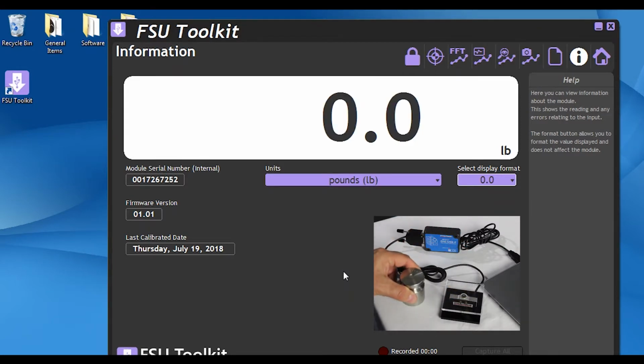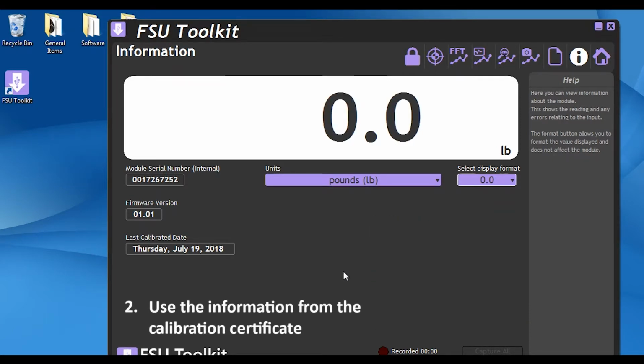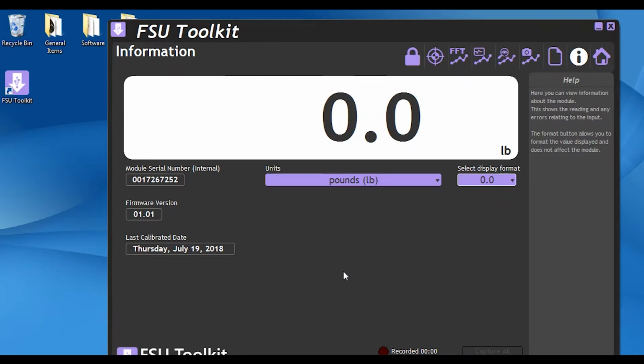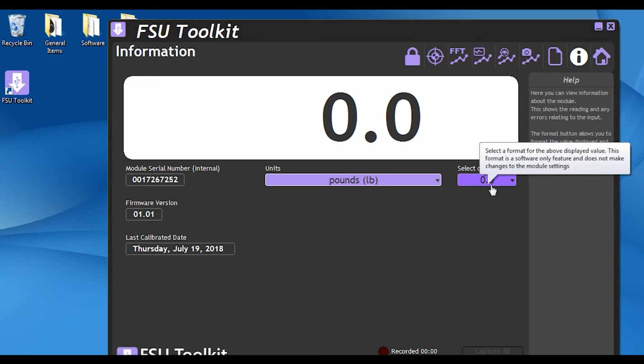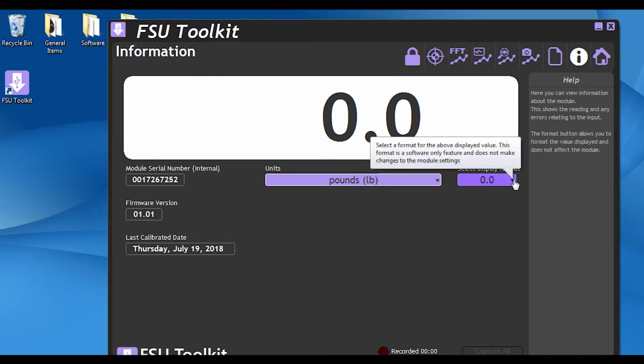Now we're going to show you the second calibration method. This is called the table method, and what we're going to do is use information from the calibration cert, type it in, and then it will calibrate the DIG USB-F to match the calibration cert. So the first thing we'll do again is to make sure the unit is correct. In this case, pounds is correct, and as a reminder, we can use the drop down to change our unit. We're going to select the display format, and we want 1 unit to the right of the decimal point, which is what we have now, but again, we can drop down and change that.